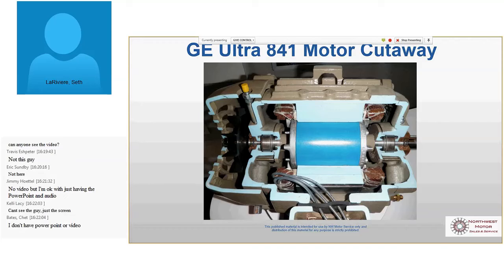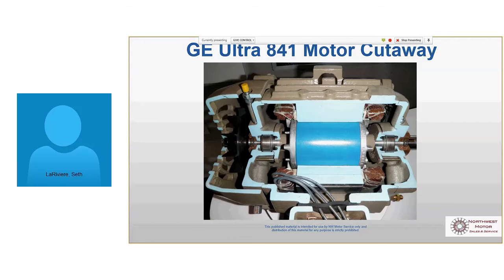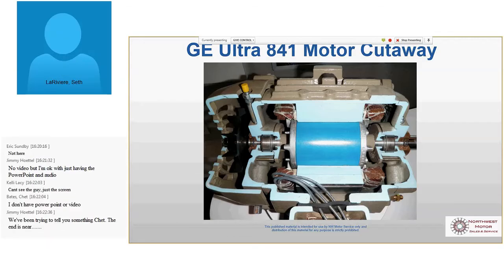There's some other neat features here. This, I know you can't really see here. There's 3 phases here, A, B, and C. And they're separated here with probably Mylar or Nomex. Yeah. And the other thing is the bracing. All these end turns are tied. So you can kind of tell when you open a motor and just look at a cross section of it, the frequency and the increments of that bracing kind of tells you a lot about how well that motor was made. Inexpensive motors, you might see bracing every several inches.